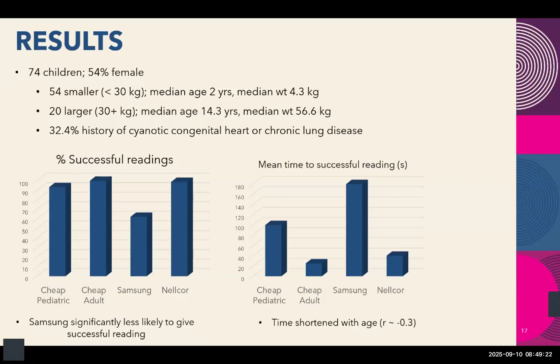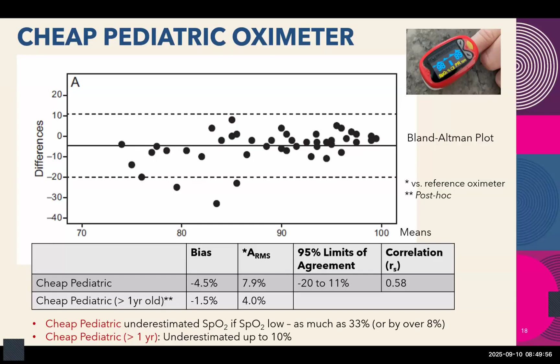So if we look at these devices one by one, in terms of the cheap pediatric oximeter, the bias was minus almost 5%. So the values that it was reading were significantly lower than the patient's real values. Its ARMS by FDA standards was pretty terrible. It was about 8%. And you can see on the Bland-Altman plot that it was fairly accurate when your SATs were more than about 90. But when it was less than 90, the values were really all over the place. They were much less than the real values.